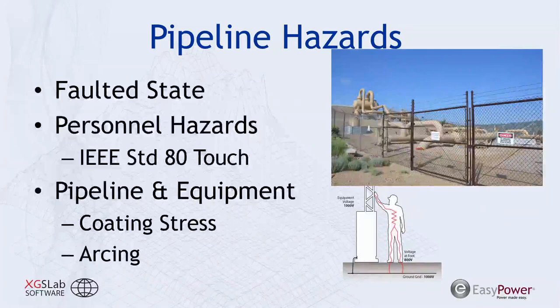Now, during a faulted state, we have other concerns to worry about. A faulted state, if you remember, we have possibly conductive coupling occurring, as well as possibly greater inductive coupling occurring. And this is over a short duration of time, but over that short duration, a person could be exposed to hundreds of volts. And often when we're looking at a personnel limit or what is an acceptable voltage limit for applying any sort of mitigation to a pipeline, we can use some of the calculation methods that are provided in IEEE standard 80. And if you're not familiar with this standard, it's the standard for a substation's grounding system. And in there, it provides calculation methods to determine a survivable voltage level for personnel working on the pipeline, or in this case, in the substation.